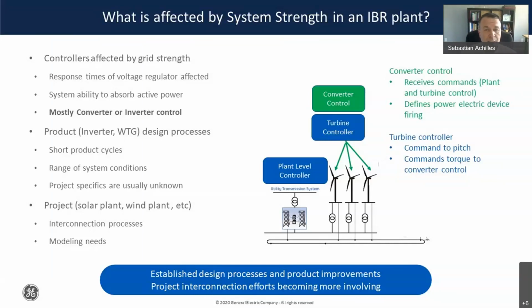Another comment: since a vendor intends to sell thousands of turbines and inverters per year, it's the preferred approach to have configurations of settings for this equipment. So you might have a weak grid configuration and a strong grid configuration, but you try to avoid tuning the controls of the converter for each individual project, because otherwise it gets pretty tough from the bookkeeping point of view, and there's a risk of mistakes if every plant is configured differently.